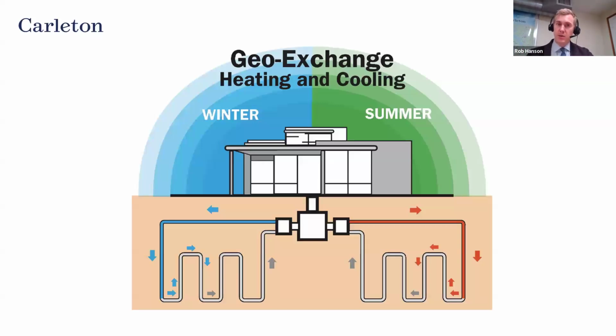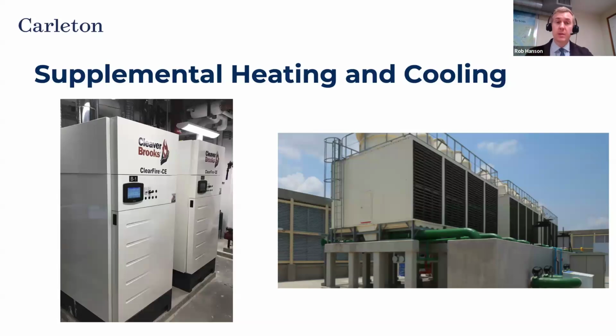So we installed a big geo-exchange system. We have about 300 bores on campus. But we knew this alone wasn't going to provide all the heating campus needed, so we were going to need some supplemental heating and cooling. On the left, you have natural gas condensing boilers. On the right, you have chillers.